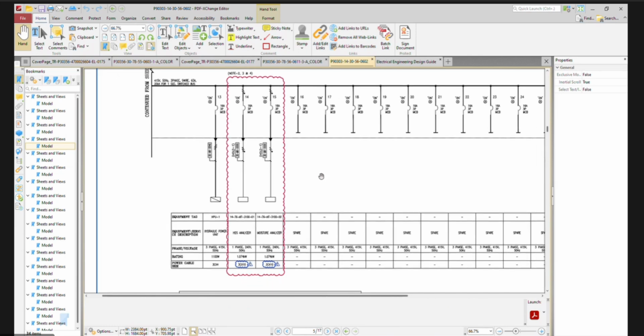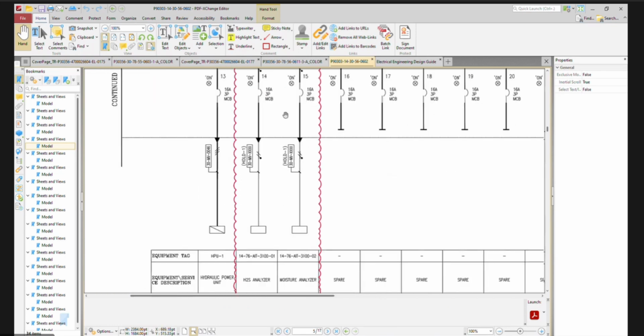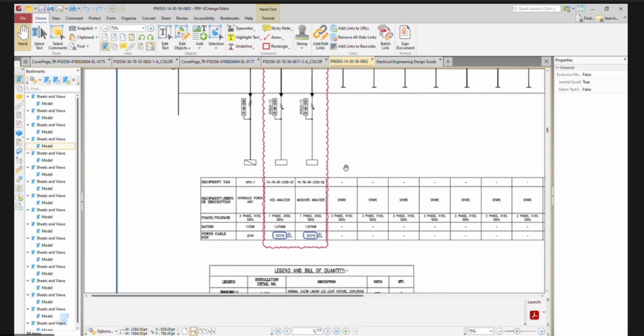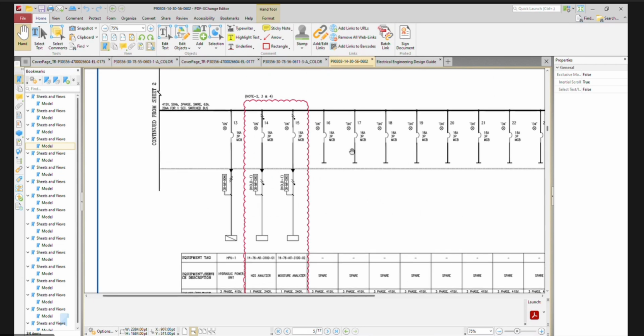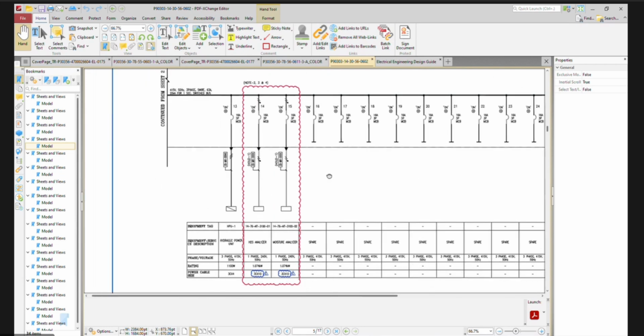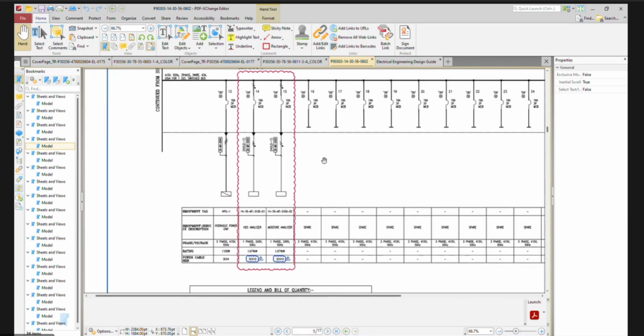That's okay. Normally ELCB is provided for handheld equipment, and it could also cause nuisance tripping, which we don't want for such equipment. If you think it's mandatory we can reconsider, but actually, as per the requirement, handheld equipment used by operators or maintenance people should have ELCB, while fixed equipment should use MCB.